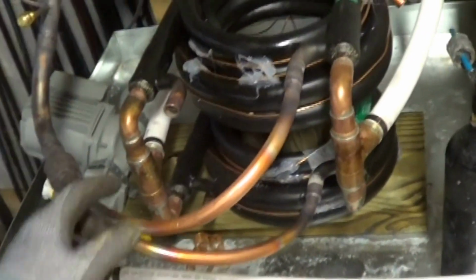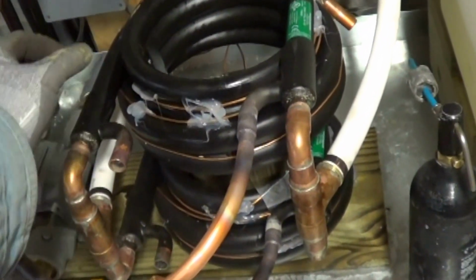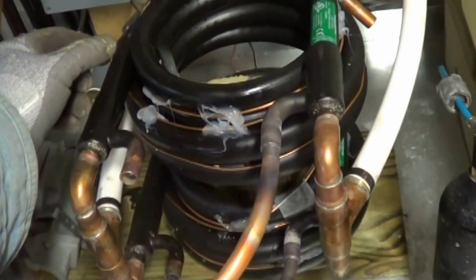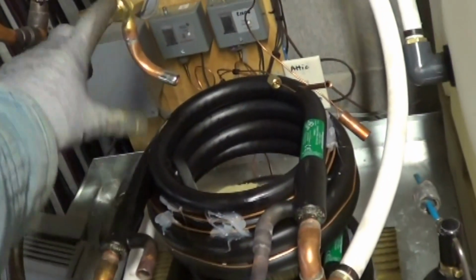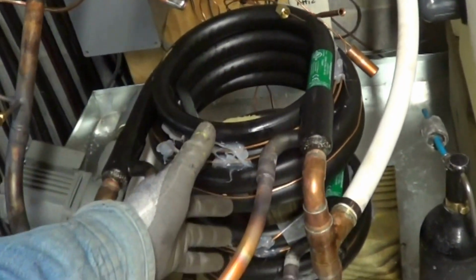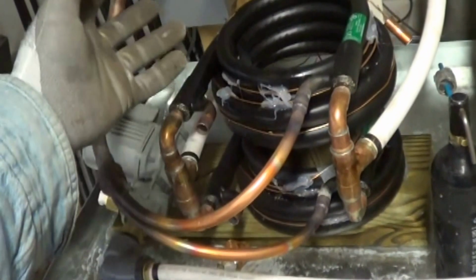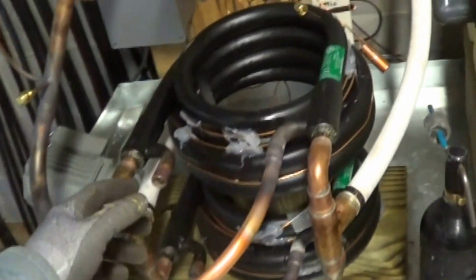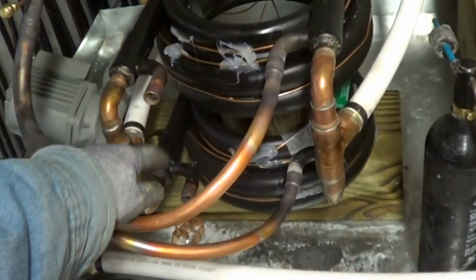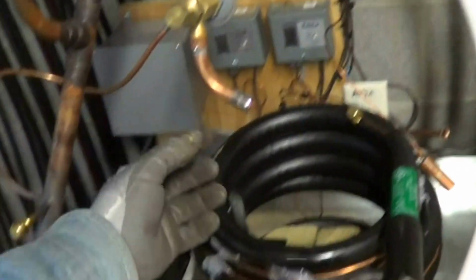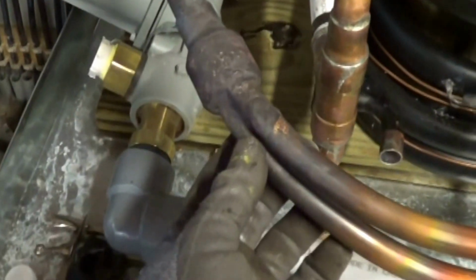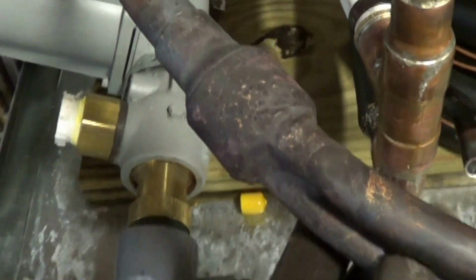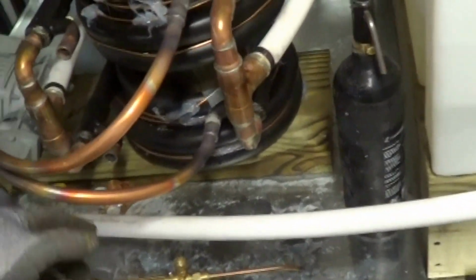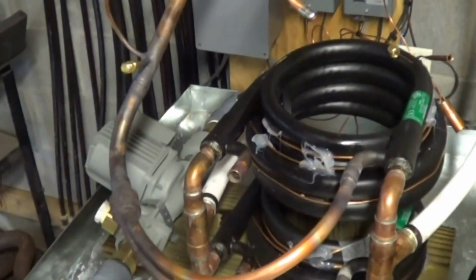There's a lookup table for what size you want your feed capillaries to be. 5/16 rates at 2.5 tons. You want a 2-pound drop on your feed capillaries to also ensure equal feed on both coils, and also large enough to handle the reverse cycle heat pump. So on these we're going to do 5/16 going in vertical, and a similar setup like this, which I just made out of a cap. You can see there. Now all this slag would be on the inside of the pipe, so it's important to have CO2 inside the pipes when you solder, so the pipes stay nice and shiny.